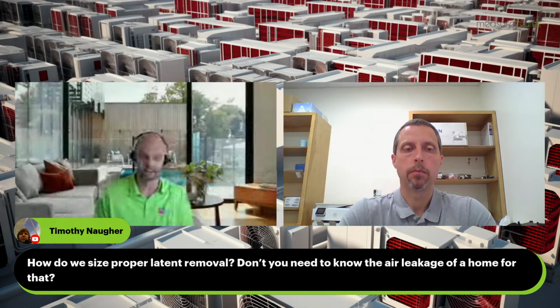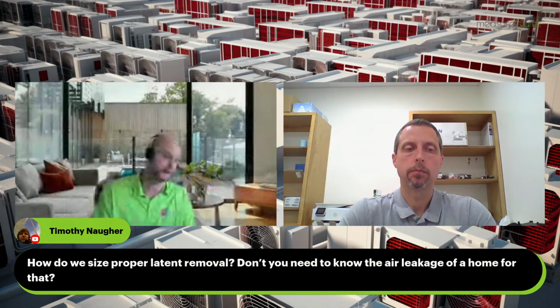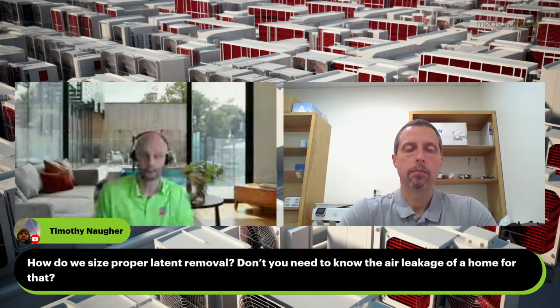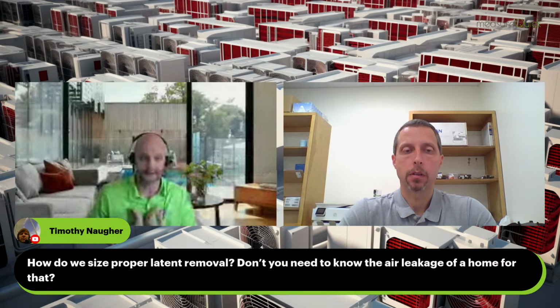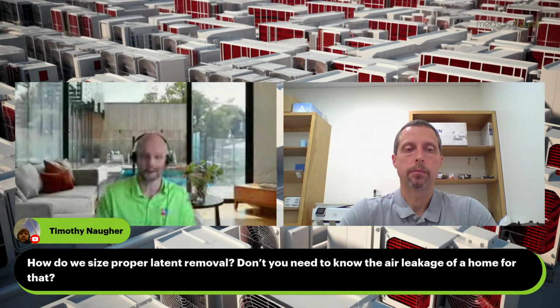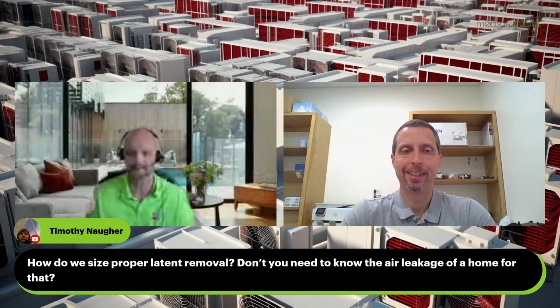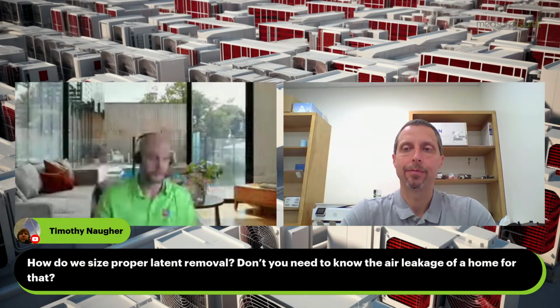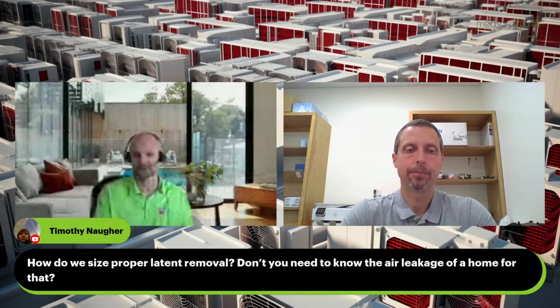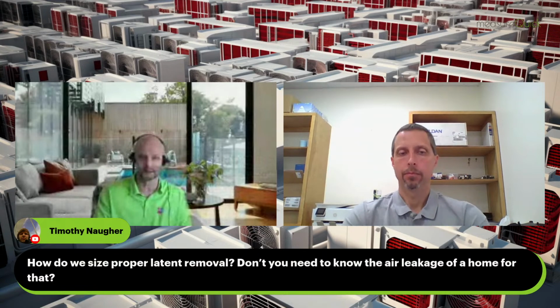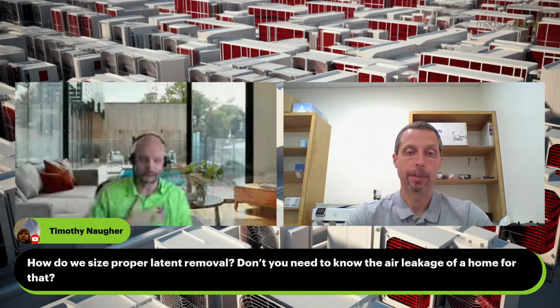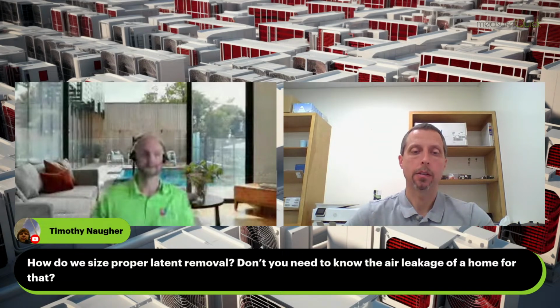But when it comes to air leakage, you have to come up with some kind of way. If it's not an existing home and you can't go out and put a blower door on it, it's my advice to come up with a way to design to some kind of predicted air change number, because the other way is just guessing. I mean, it's a WAG, a wild ass guess, when it comes to predicting if the house is tight or loose or whatever those old metrics are. I have thrown those things totally in the garbage and I don't use them at all. But that's my personal design methodology.